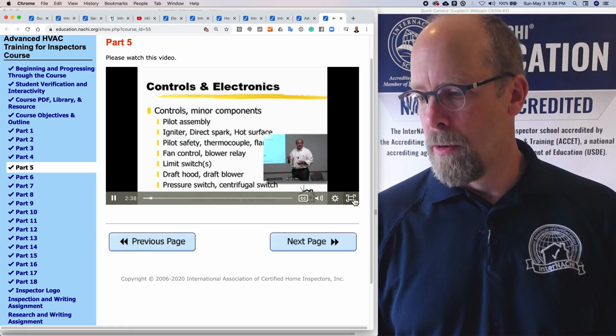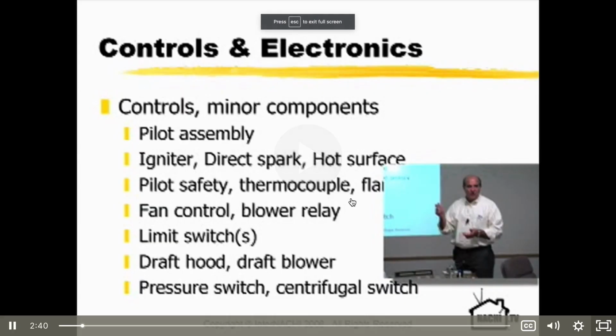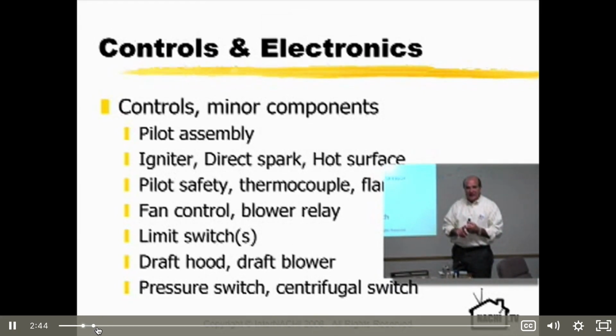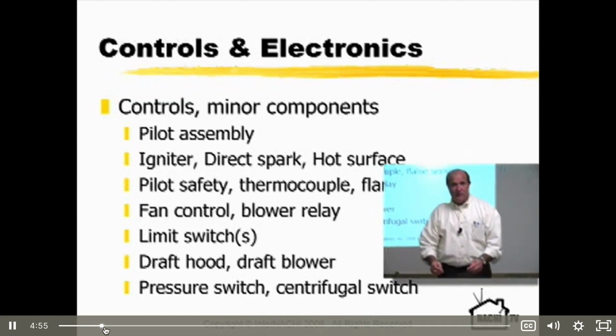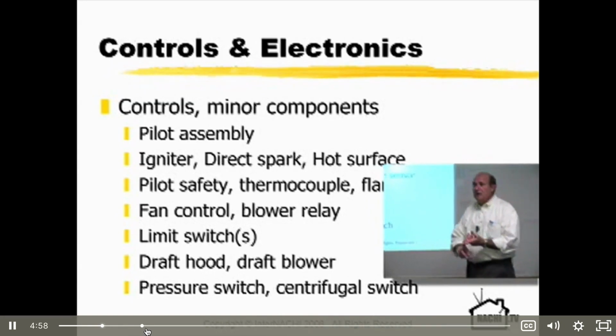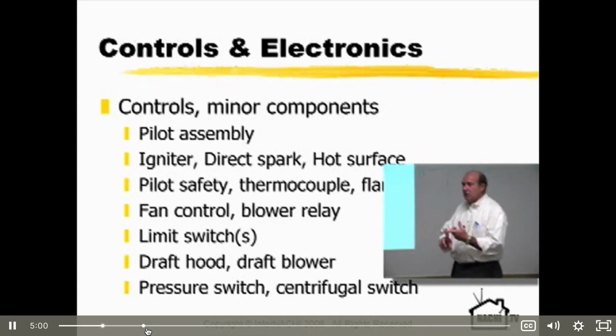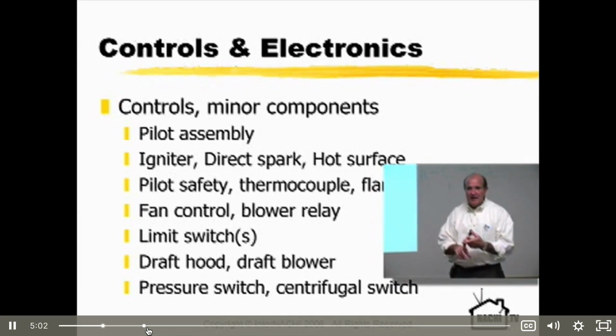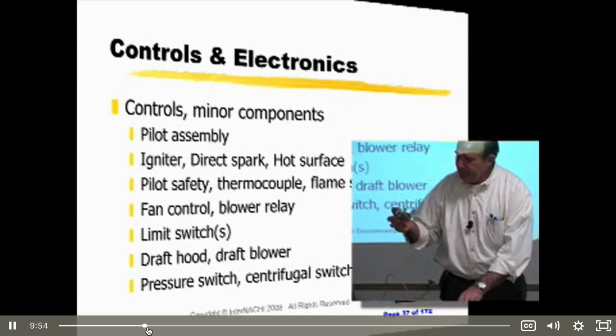Gas burners are on, so look for an improperly adjusted pilot light. If you hear that igniter ticking away, clicking or rapping while the burners are still on, that's not a proper condition. We need continuous ignition and good flame, and then it's okay to keep injecting raw gas into that heat exchanger.